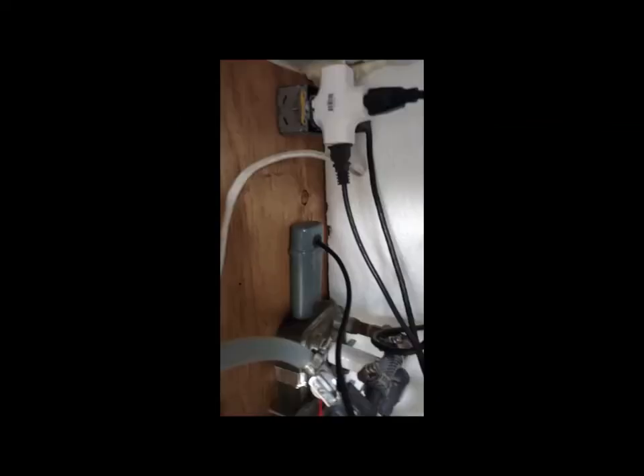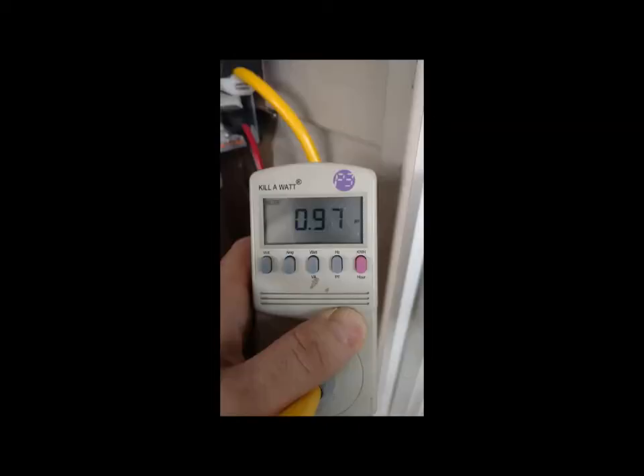Here we see the capacitor plugged into the switched outlet. The power factor of 0.97 helps with the LED lights. The inverter does not really see any reduction in power draw from the battery. Here we see -7 amps at 48.3 volts, but as best I can tell, inverters like I have don't struggle making reactive power, but it does create a little bit of waste heat. So getting that power factor closer to 1 will save maybe 1 to 2% in efficiency.